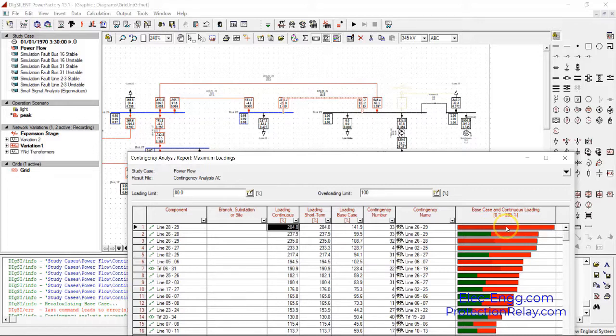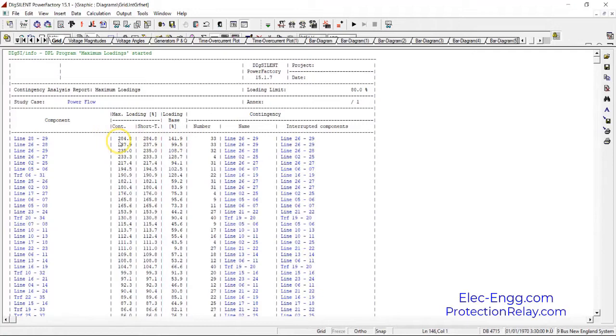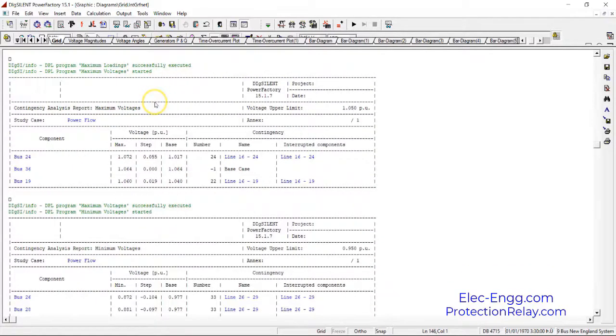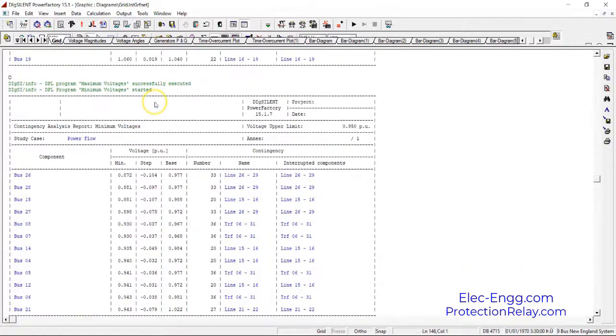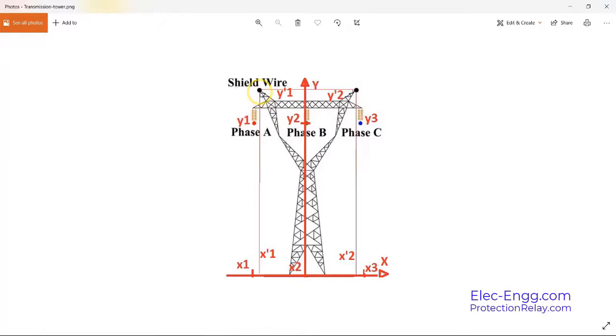141 and it's red because it's overloaded, and after that it's increased to 284 percent after the contingency. For maximum loading, maximum voltages, minimum voltages, and shielding wire or earth wire here.